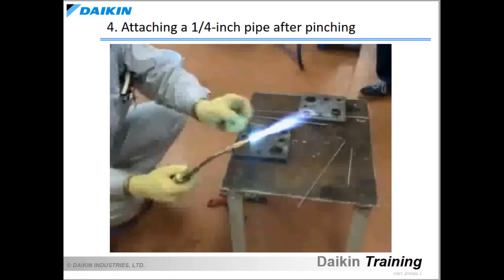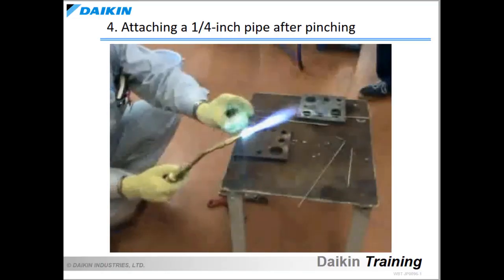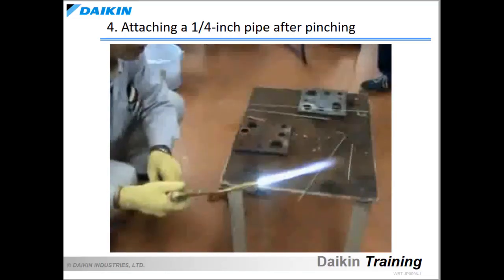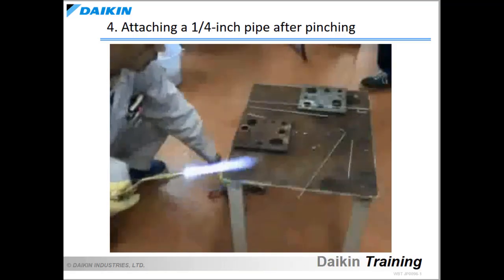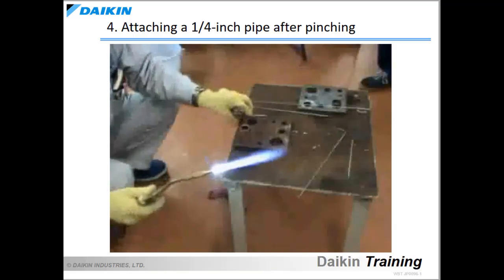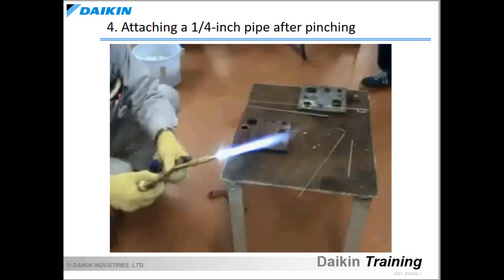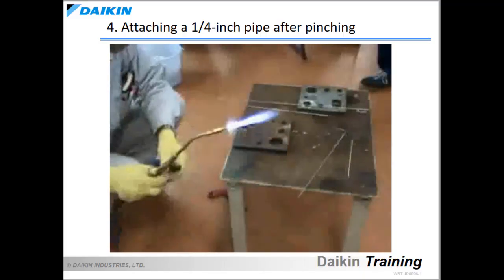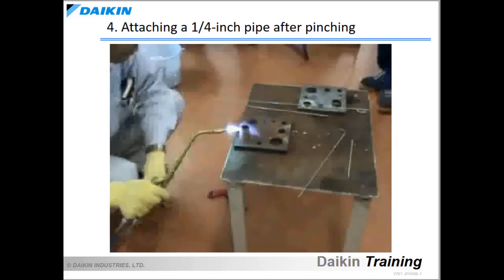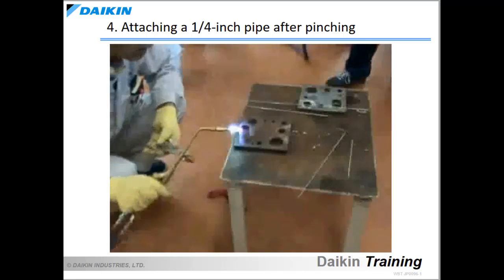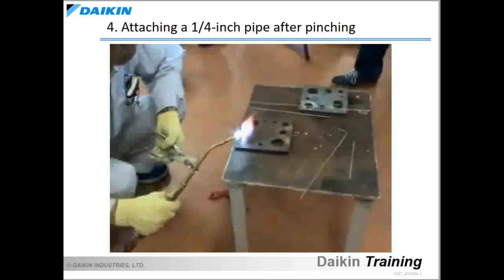Let's now learn about the method of attaching a smaller pipe to a larger pipe, which is commonly used as a jig for the air tightness test during installation work. Use the reducing flame and adjust the carbonizing flame to a length of approximately 2 inches. In order to anneal, first heat the entire circumference of the larger pipe evenly until it becomes red.